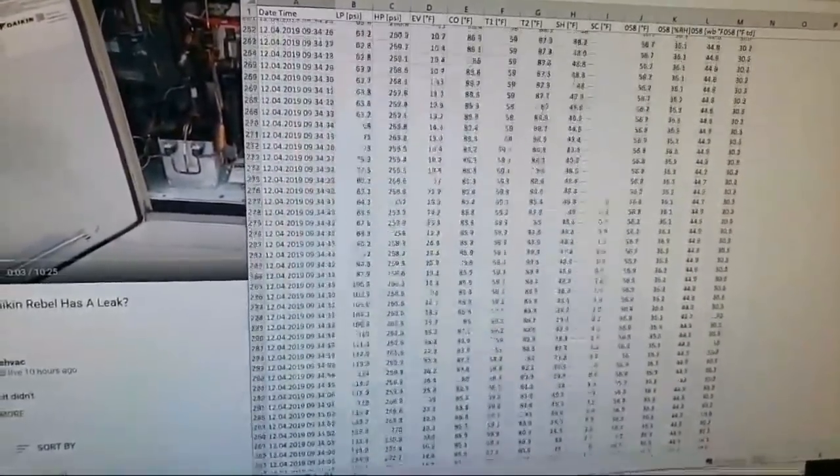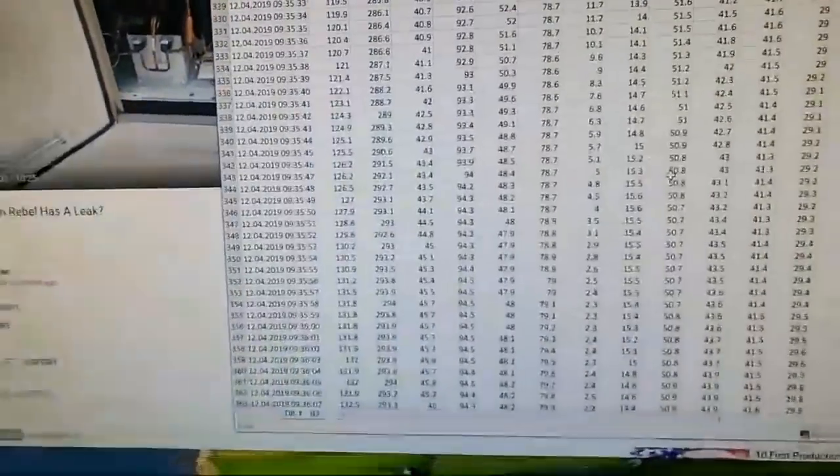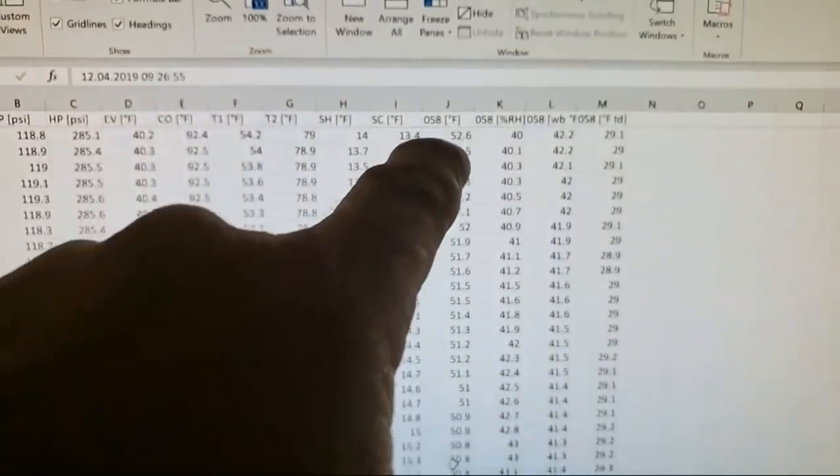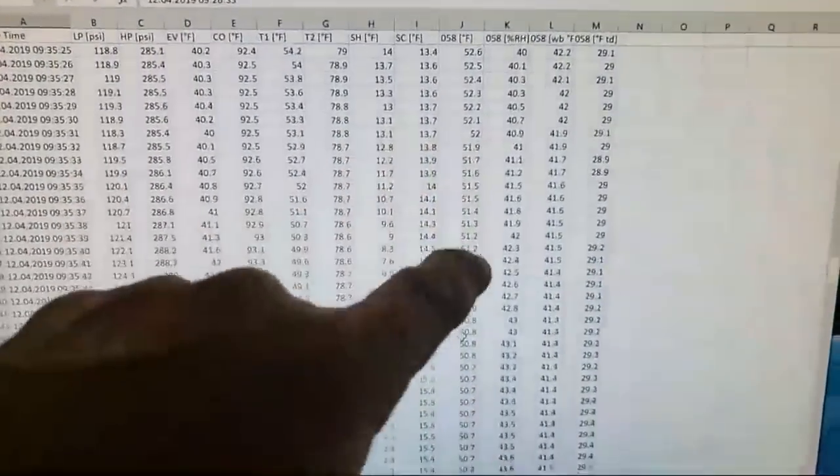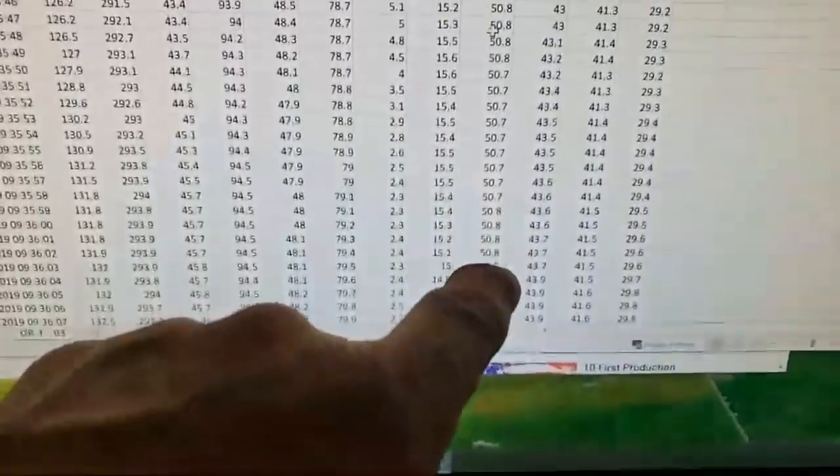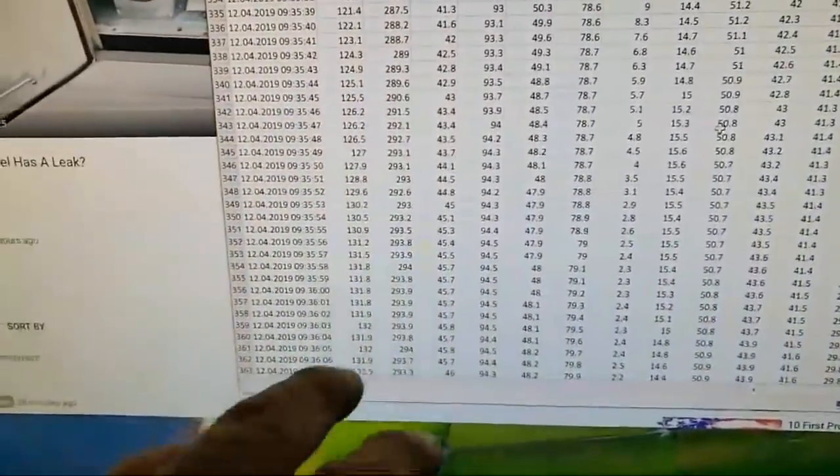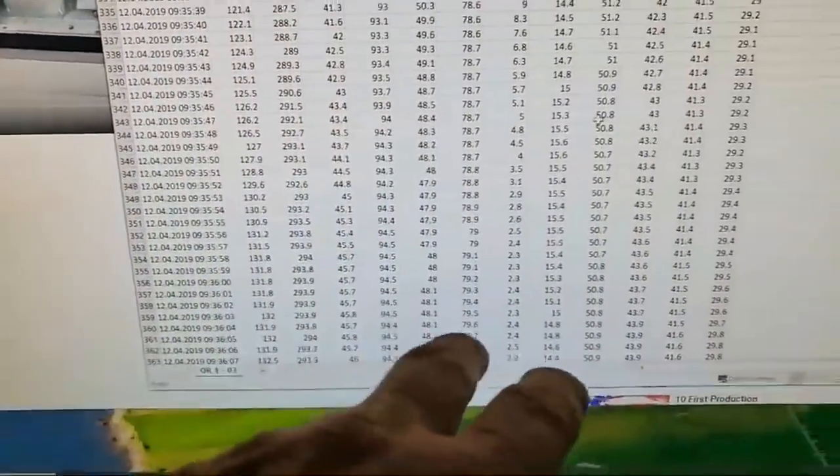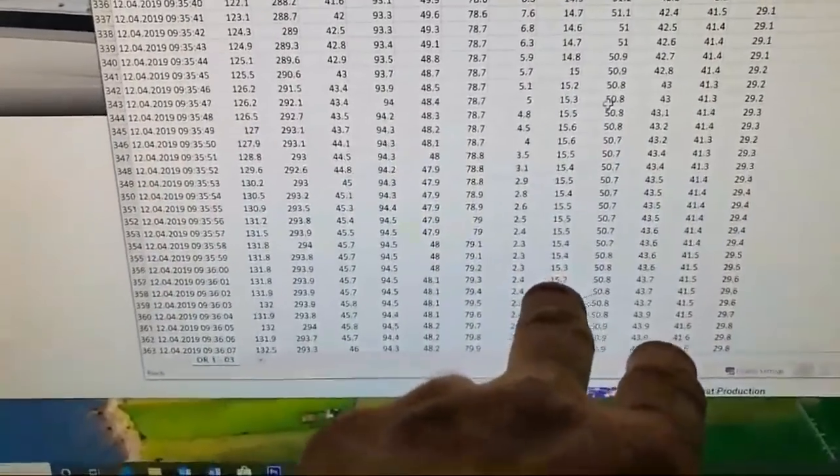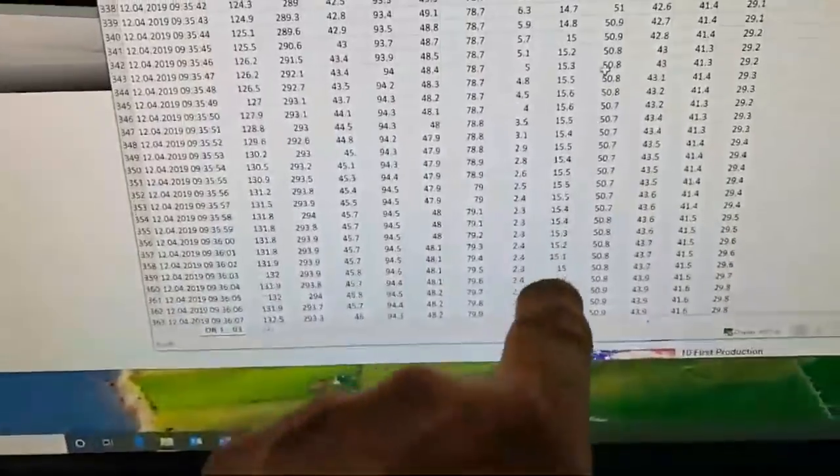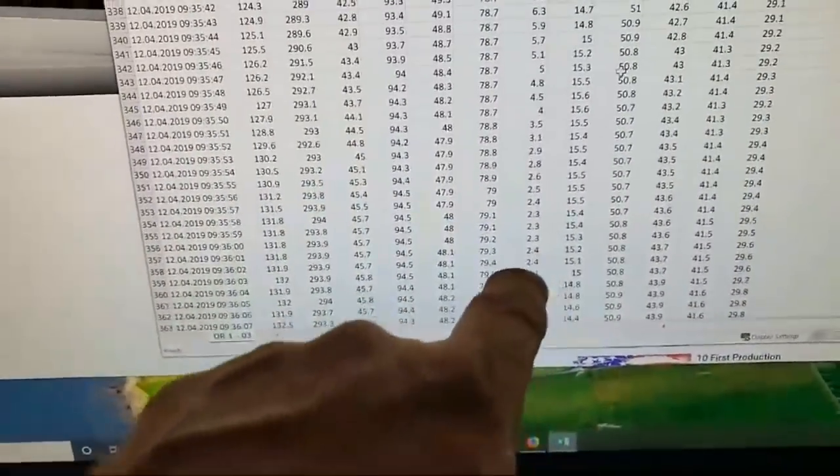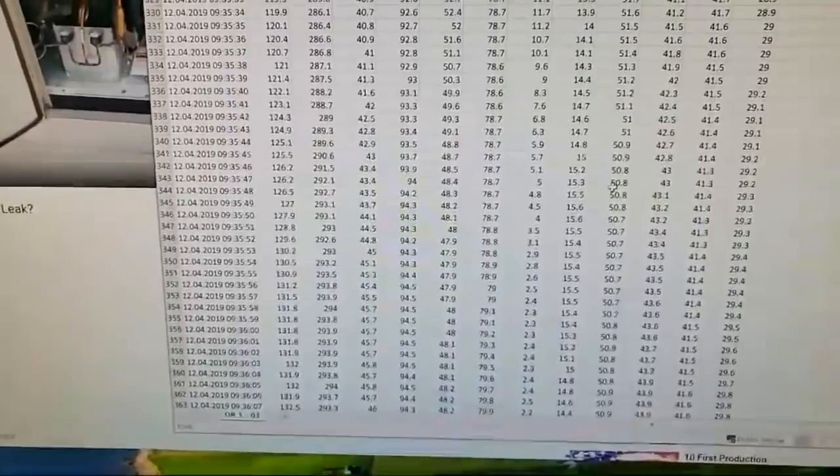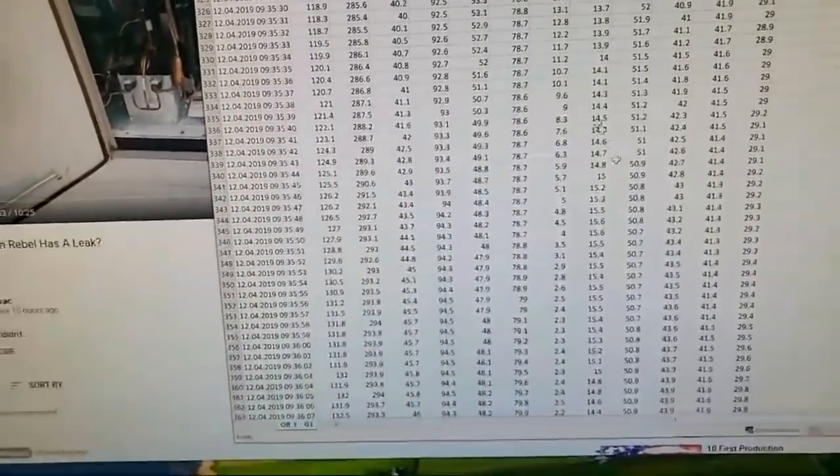There's like no subcooling. But then once everything starts balancing out, there's adequate subcooling and the superheat corrects. So, wouldn't I say that started at 841, basically. And it runs and runs and runs. And it's ramping up and everything, too. And evidently, the electronic expansion valve is just not fast to open. I thought it was sticking by the time I checked this thing out. And then here we are. It's just kicking ass mode. 289, 290, high discharge, 120-something suction. It's about 7 degrees subcool, 11.7 superheat.